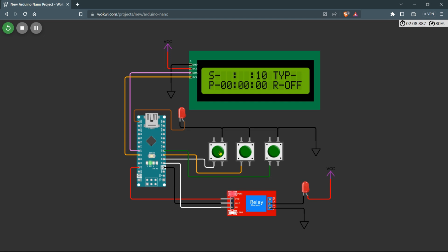In type C, the relay operates in cyclic timer mode, which means that it follows a recurring pattern. In this mode, the relay is initially activated for a specified duration, after which it is automatically deactivated for the same duration. This cycle continues to repeat automatically, allowing the relay to alternate between activation and deactivation at regular intervals, without the need for manual intervention.